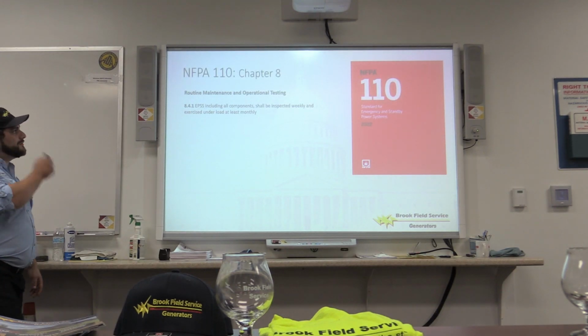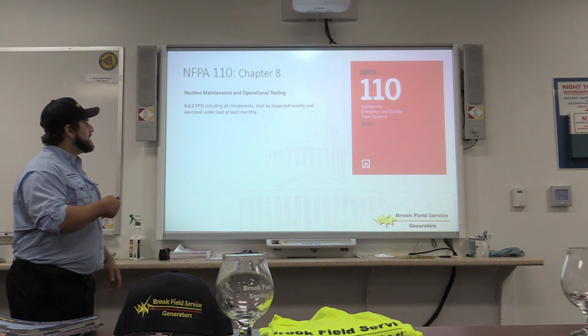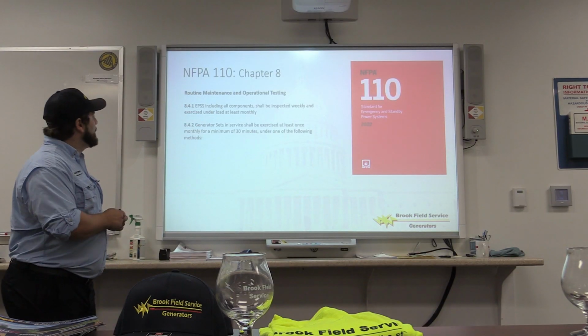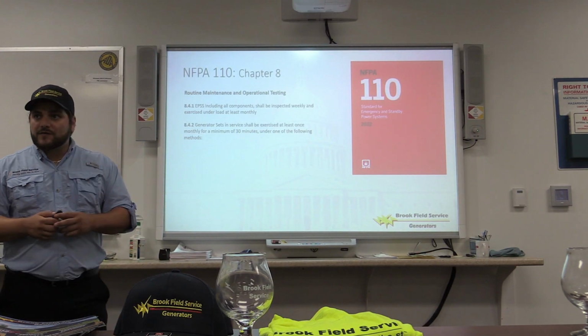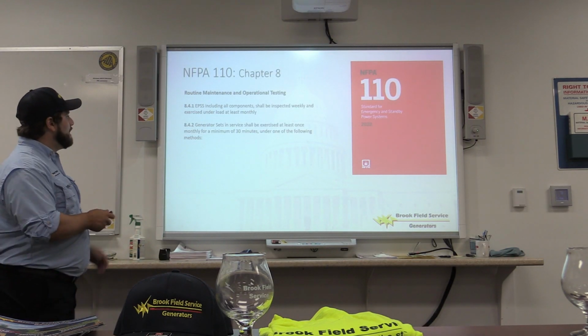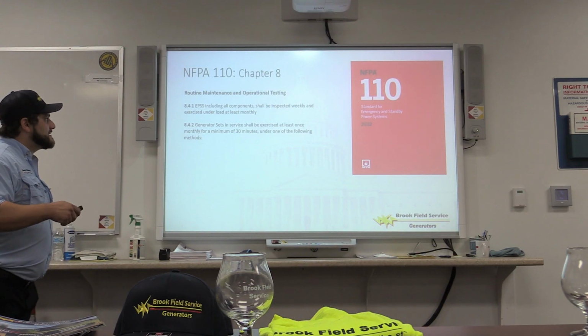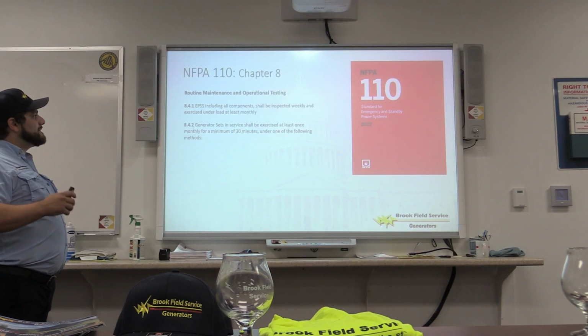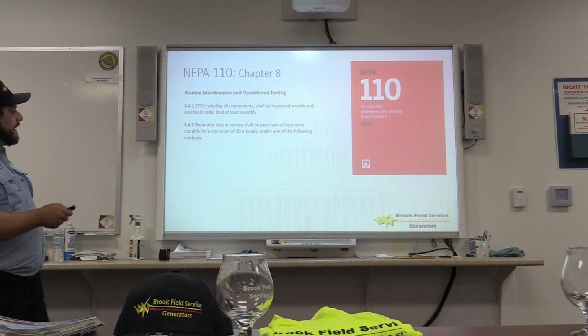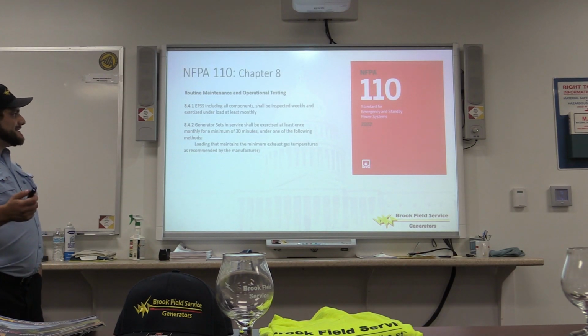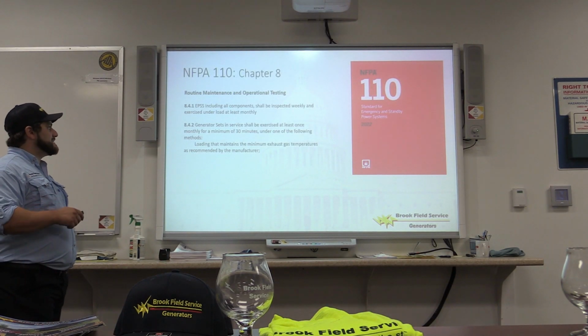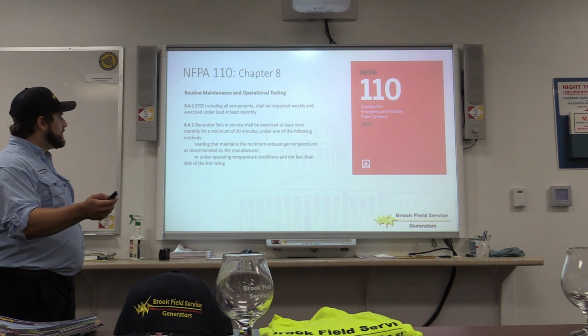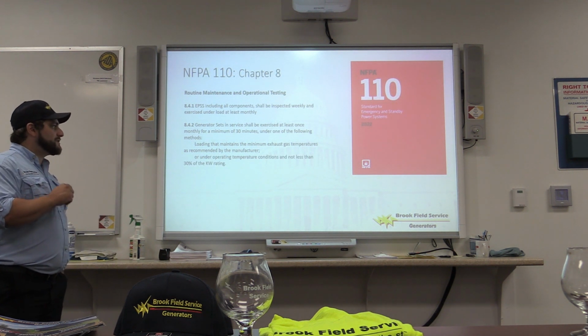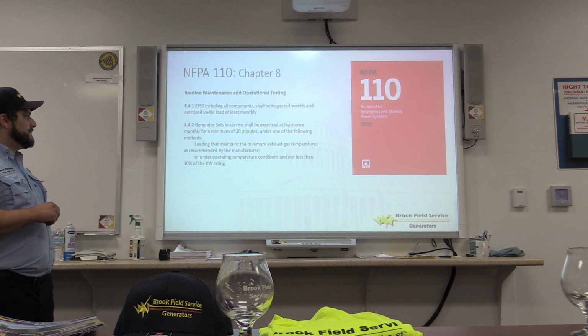EPSS, including all components, shall be inspected weekly and exercised under load at least monthly. So that means at least getting someone out to all your sites, just giving a visual check over. Generator sets in service shall be exercised at least monthly for a minimum of 30 minutes and under one of the following methods: loading that maintains the minimum exhaust gas temperatures as recommended by the manufacturer, or under the operating temperature conditions and not less than 30% of the kilowatt rating.